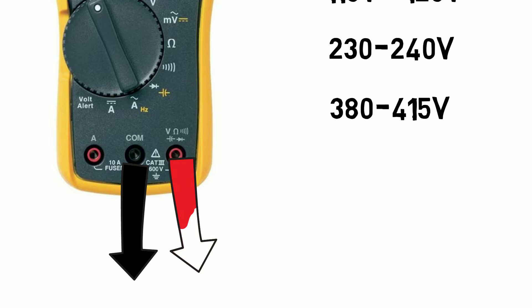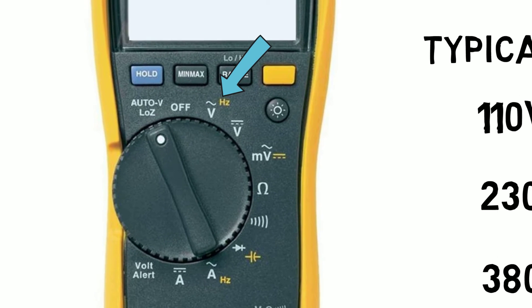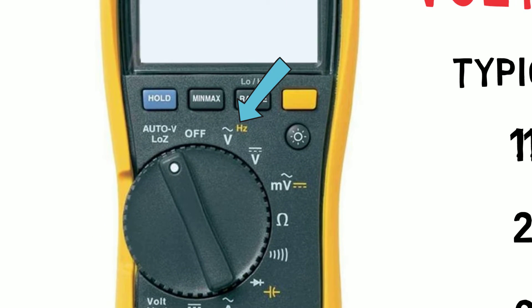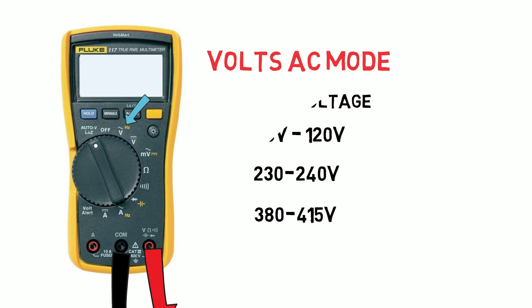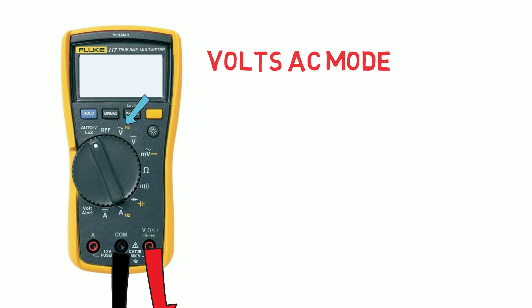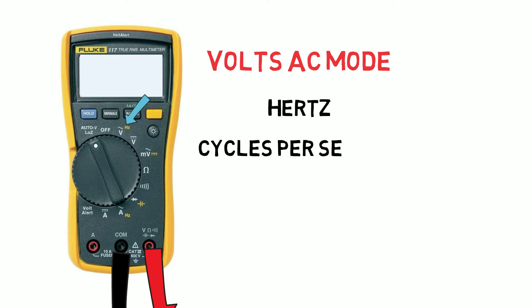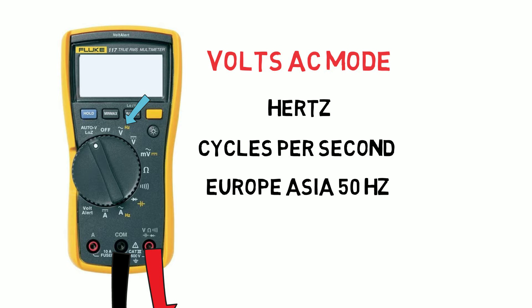Our probes connect between whatever two conductors we are checking voltage between. In single phase applications this is usually between live and neutral, and in three phase applications we will be measuring between the phases or phase to neutral or earth. If we press the yellow function button while measuring an AC voltage we will be able to determine its frequency measured in hertz. A hertz is how many times a second the alternating current voltage cycles. Typical power supplies in the UK, Europe and most of Asia are 50 hertz, whereas voltages in the US are usually 60 hertz.